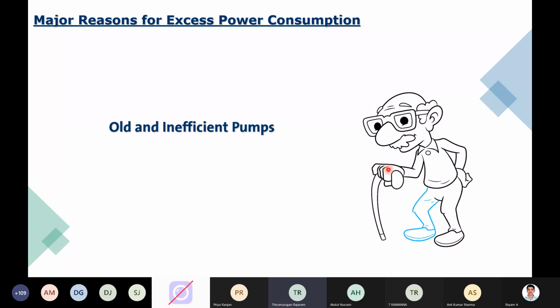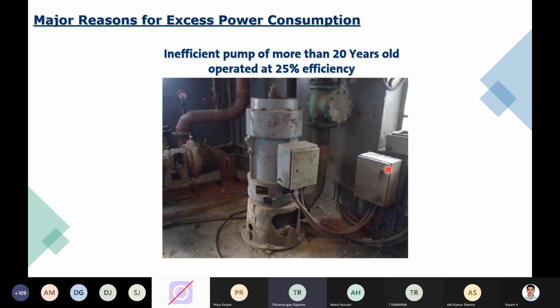Okay. The other factor is your old and inefficient pumps, which I just touched upon, where you can find, in any power plant in India, almost 30 to 40 year old power plants also, where they are trying to adopt the energy saving mode. Definitely we could see a lot of avenues there because old pumps are still being operated at certain sites. So this is one thing we could identify in an industry where the pump was 20 years old, a vertical turbine pump which is close to 25% efficiency. That is what we were able to identify. So there is a lot of scope when you talk about replacing old pumps.